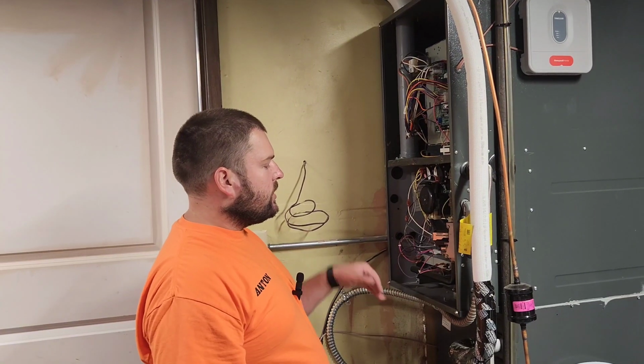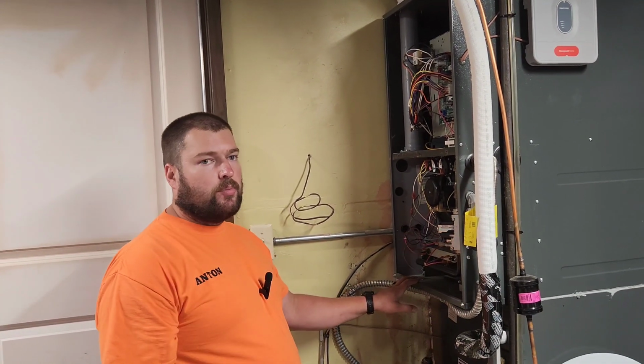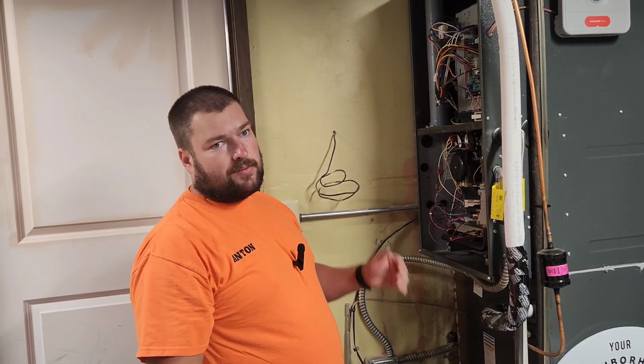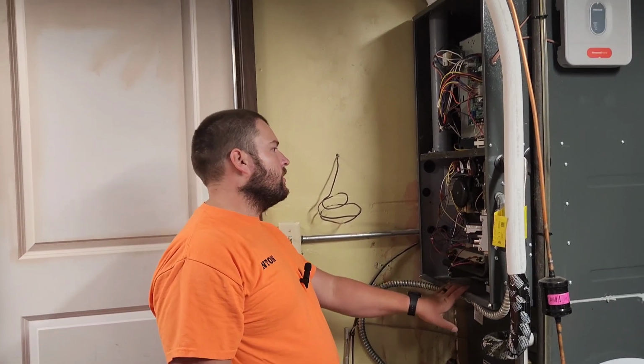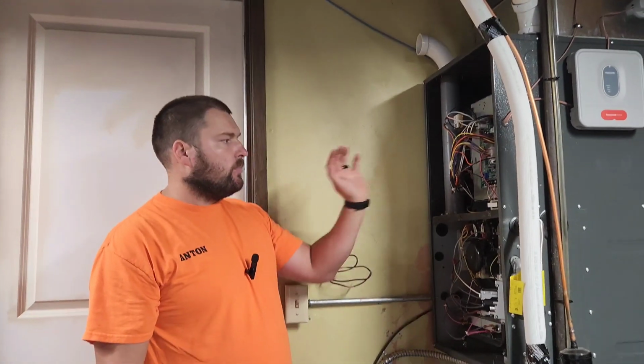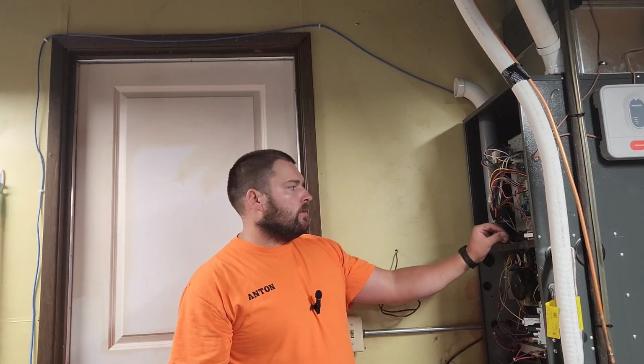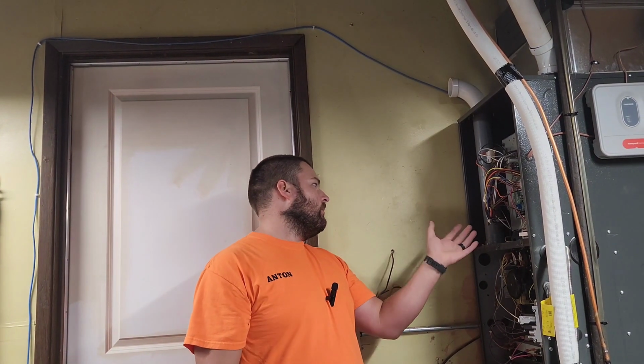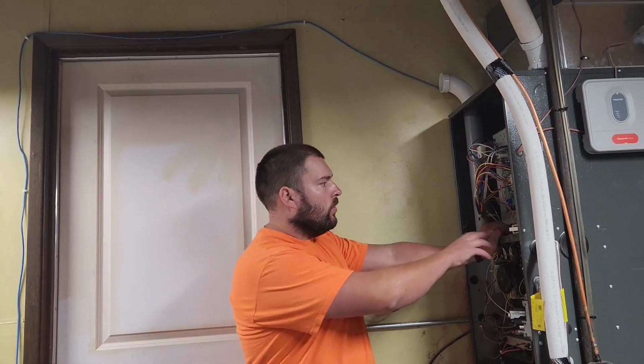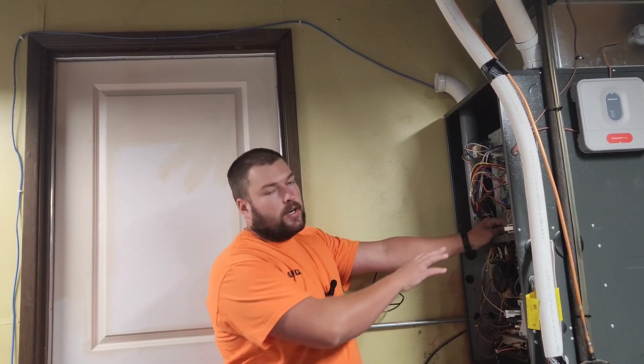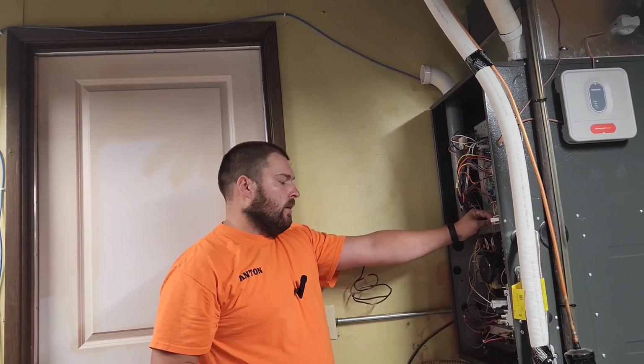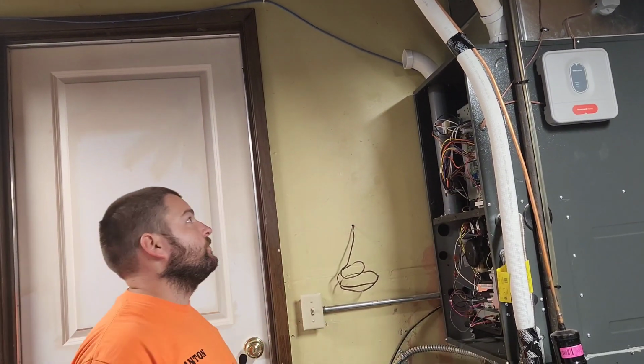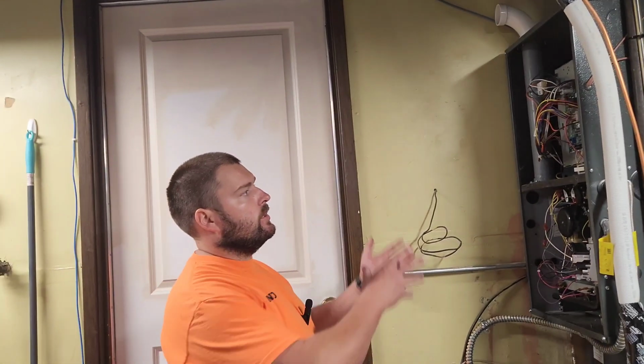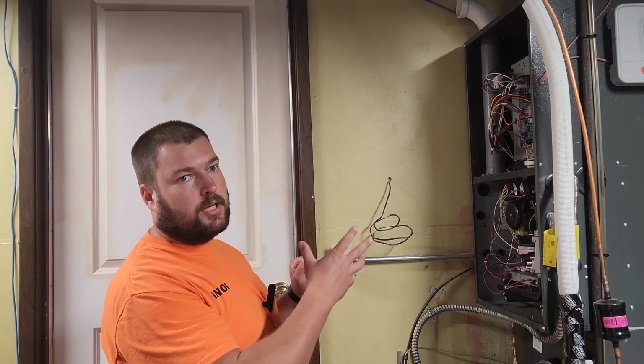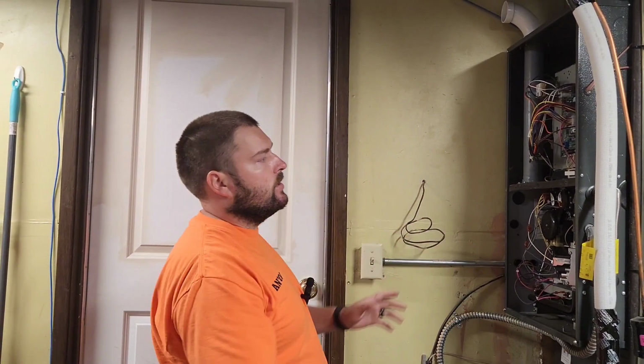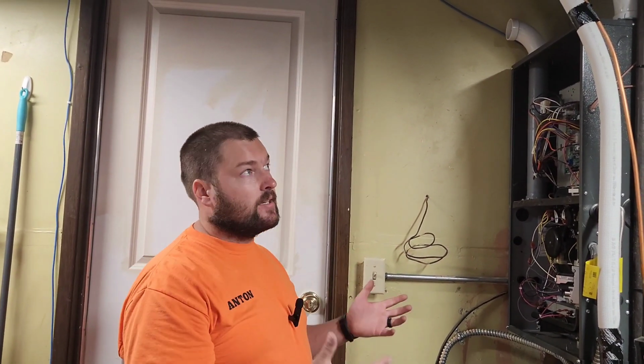After we clean the flame sensor, we'll clean out the burner compartment. These will get dirty even after a couple seasons of use. After the burner compartment, we'll move on to the blower compartment. We'll do a visual inspection here, just make sure everything is looking good. There's no wires that are starting to fray on any metal or anything. If the blower is actually dirty, we can pull the blower out, clean it, vacuum it up, and then install it again if the blower is excessively dirty.